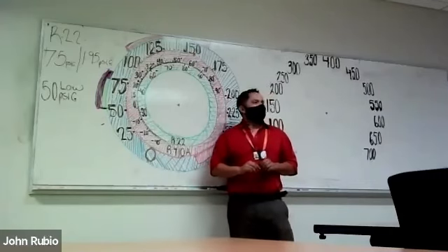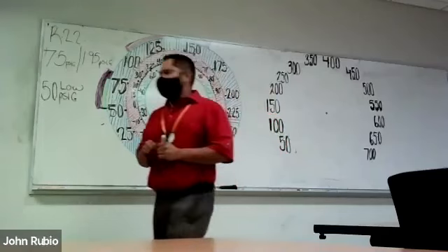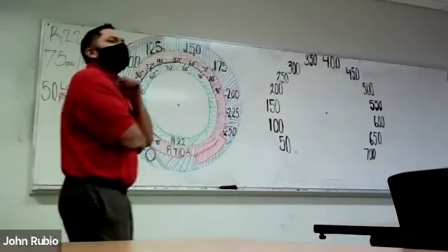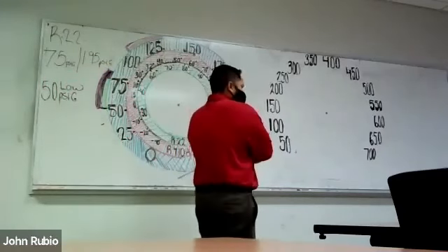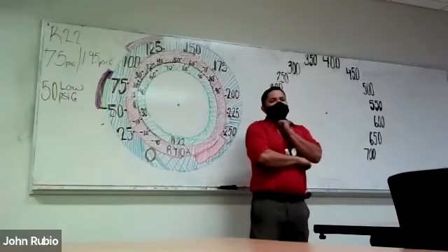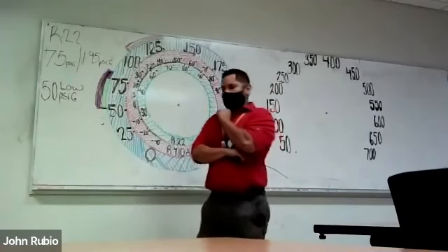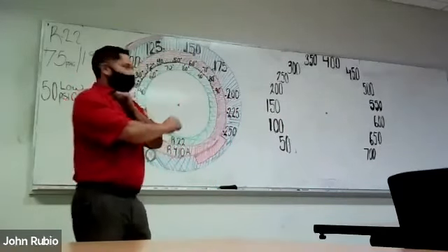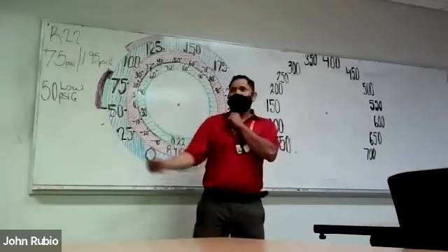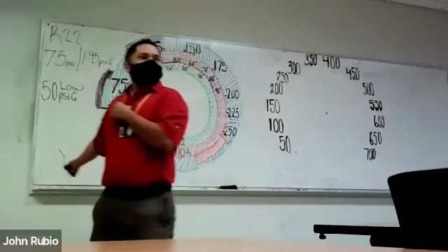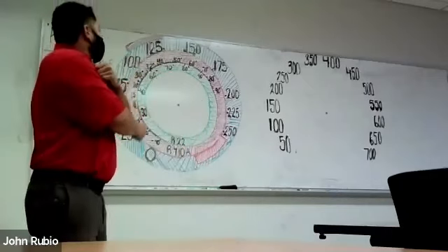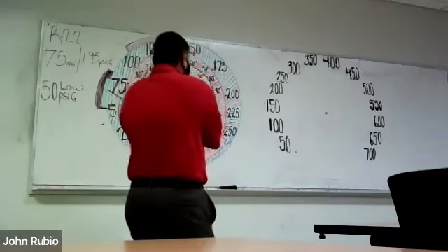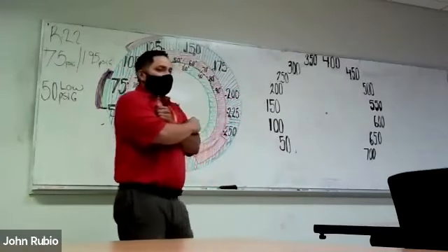What we need to notice is that when you look at your refrigerant gauges, it's very tempting to look at your PSIG. It's very tempting just to use your low side gauge. As I said earlier, the low side gauge can be used to check if a system is barren of refrigerant, which, when we looked at our troubleshooting path two lectures ago, remember we had our house that had the hot air, so we went directly to the condenser, and at the condenser we had our list, and we discovered that our refrigerant gauges were the only item on the list that could be used without taking off the panel. Well, in a case like that, we're simply trying to see if the machine's empty.